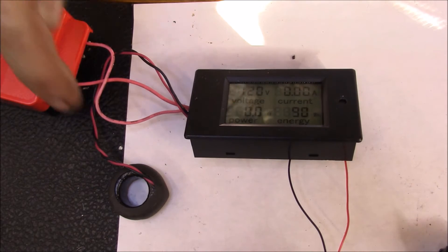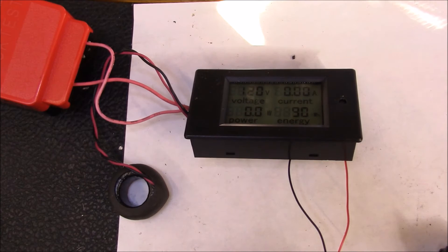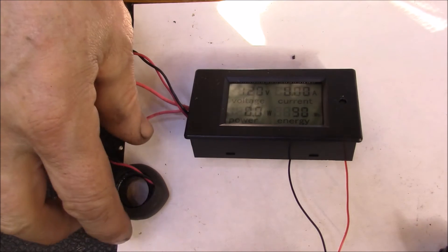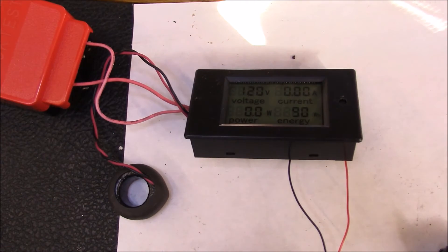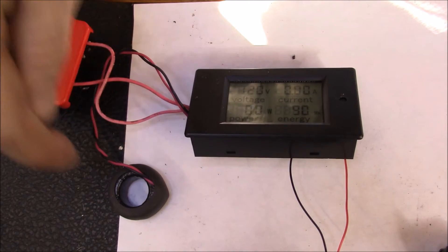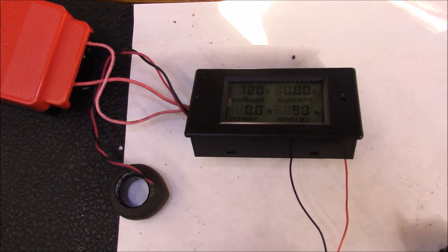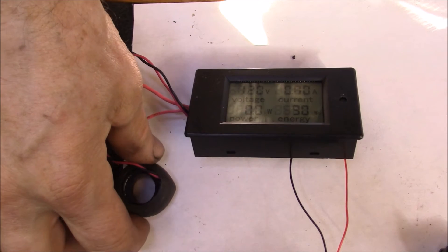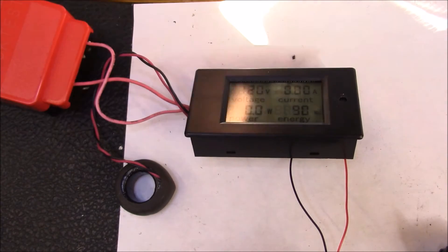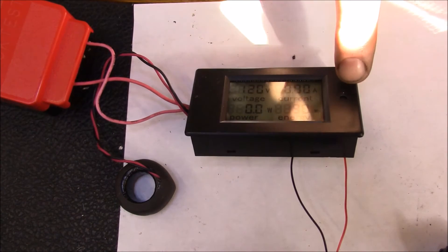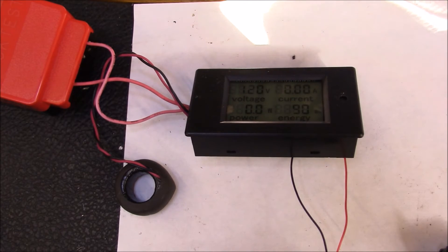I'm thinking perhaps the way the AC power supply was wired—I didn't really look into that when I installed the meter—I just kind of found wire to run through the current transformer. I may have been picking up the current or the power that's used to operate this meter inadvertently and could have been measuring its own power consumption, and that was what was throwing my meter off.